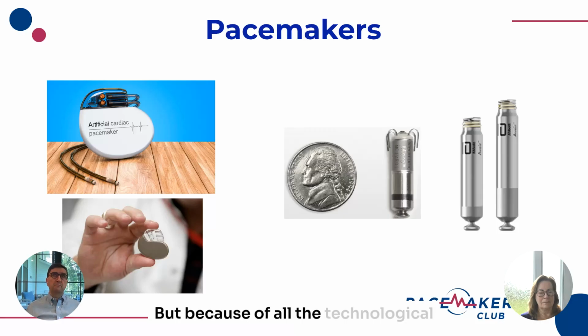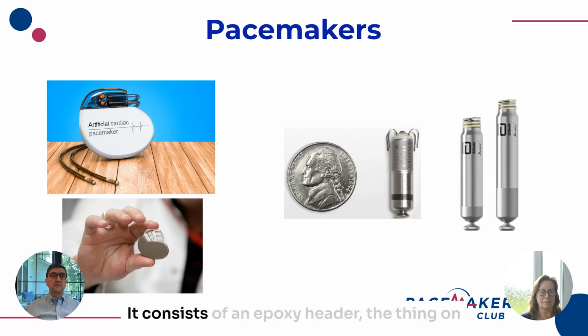But because of all the technological improvements that have occurred, most pacemakers that are implanted today are what's known as transvenous pacemakers. So in the left upper corner, you have a photograph of a pacemaker that is a dual chamber pacemaker. It consists of an epoxy header, the thing on top, which is transparent, and then the titanium can, which is the bottom part, that isolates the battery and the electrical system from the body. And then you have a couple leads that are plugged into the ports in the header.